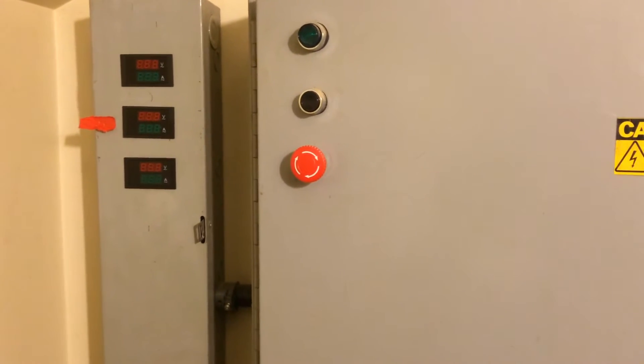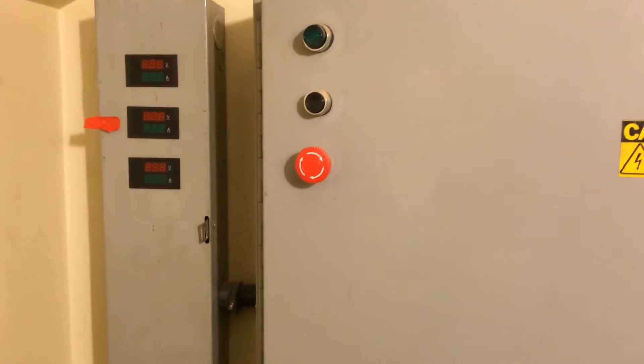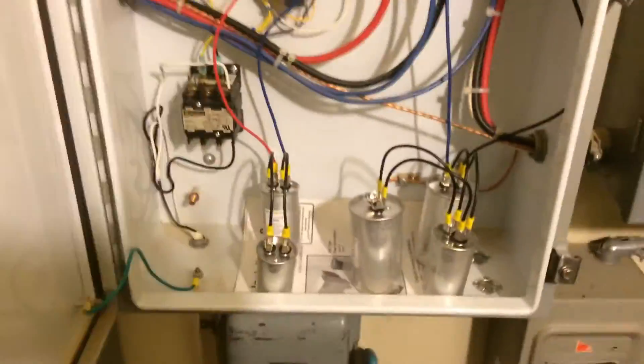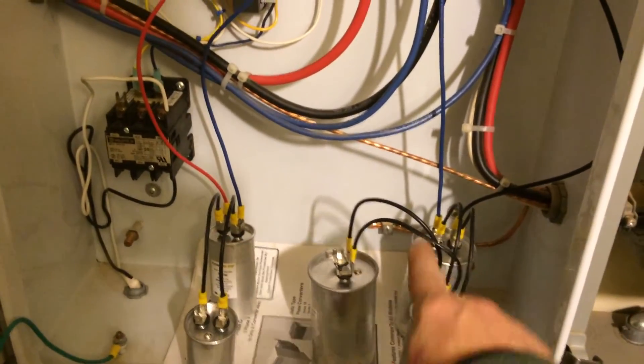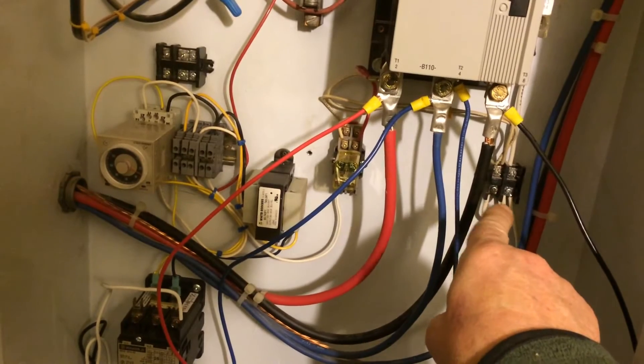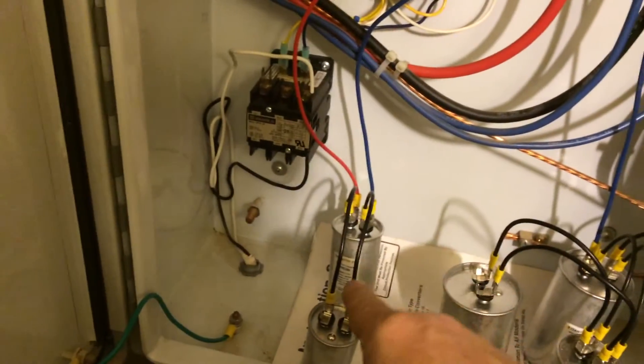On this converter we're balancing the voltages and amps at different locations. The way we've done that is by adding more capacitors to the black and blue, which is my single phase line, and red to blue, which is also my single phase line — capacitor cans just get wired between there.